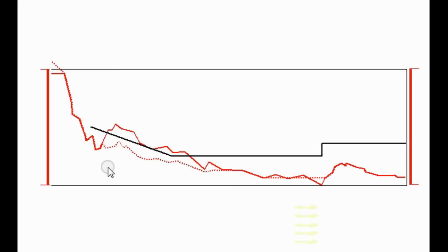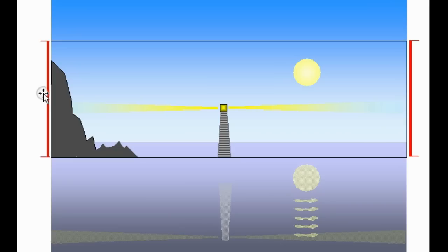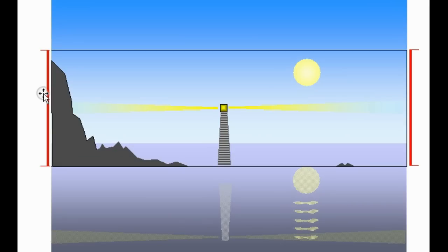We need to be able to ensure that we optimize the setting of the attenuator. And the way we do this is to go through the same series of steps that we've just been through. So if we go back to our ocean view, here we are with maximum attenuation. And we gradually reduce the attenuation, checking each time that the visible spectrum has not changed.